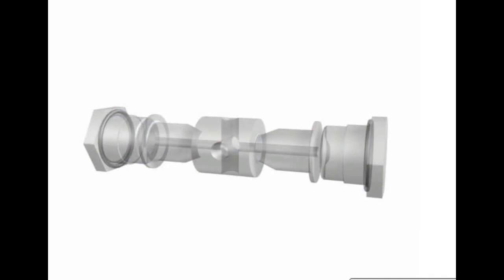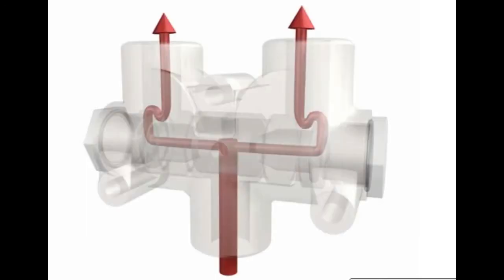Inside the housing is a sliding spool with cross-drilled holes in the center and through the entire length of the spool. The spool is able to move freely in the housing. Flow from the inlet enters the center of the spool through the cross-drilled hole. The flow divides and flows to both ends of the spool, and fluid flows out both ends of the spool.